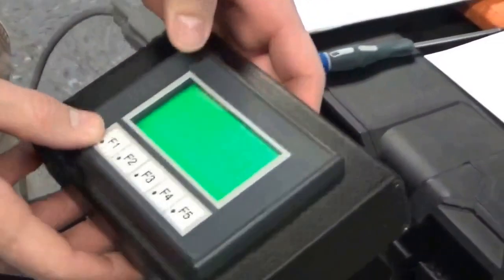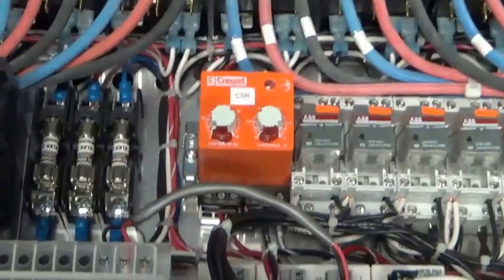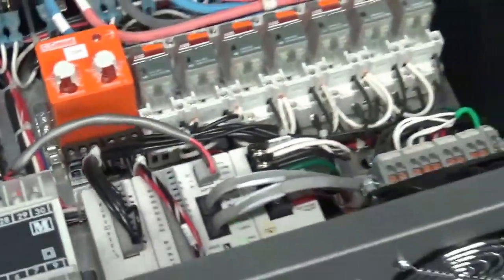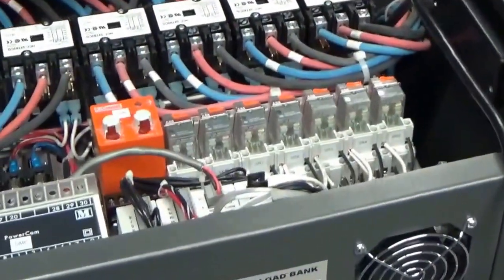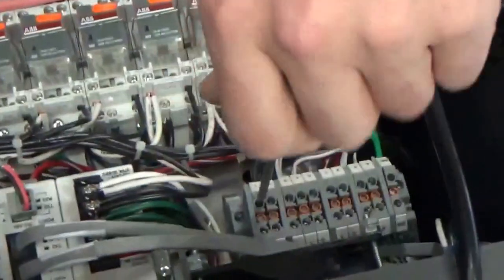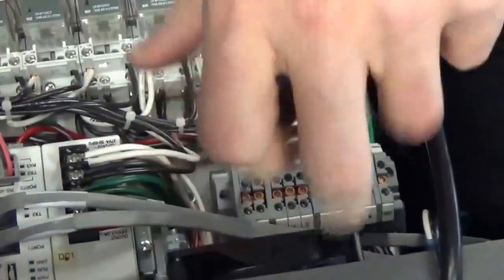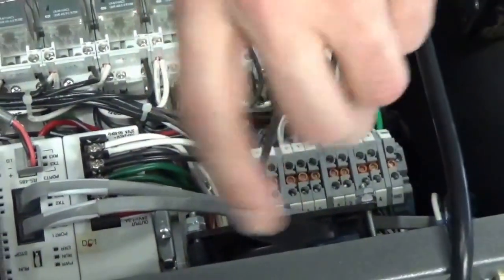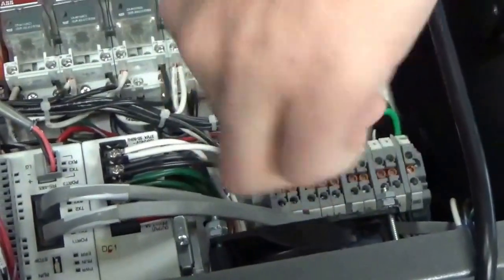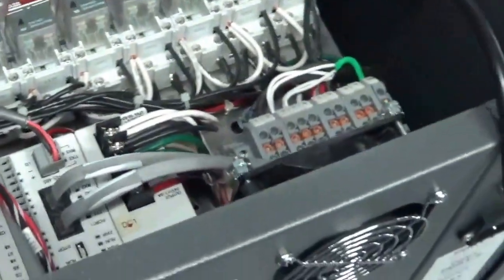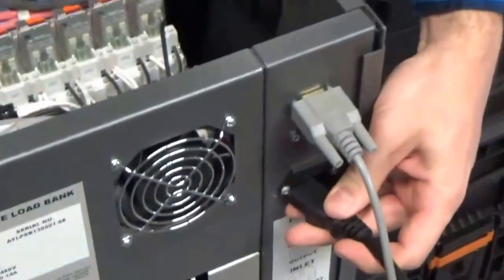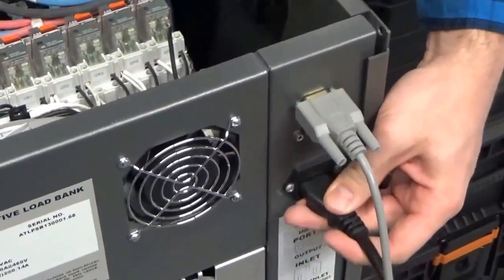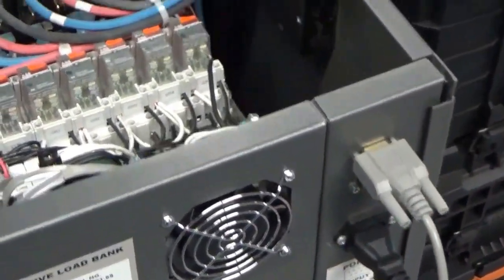What we're going to do from here is turn off control power, and we're going to run it through one more time without changing the settings on the CSR. Remove the control power. Remove that same wire you had. Turn it back down. Plug the load bank back in. Now, this time, we shouldn't see that light on the CSR turn on because we'll be in cooling failure.